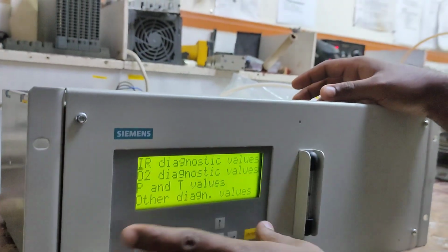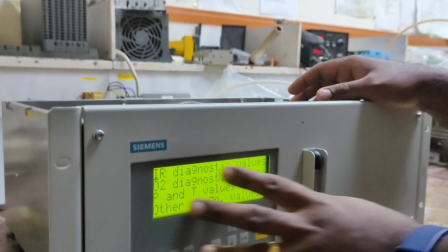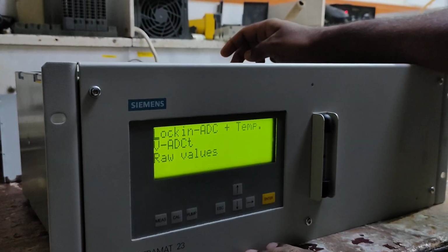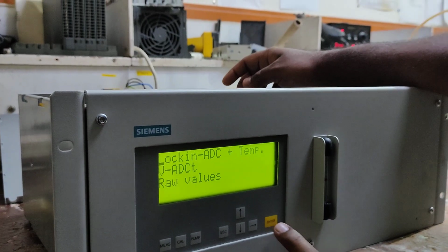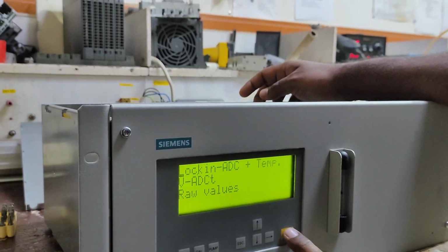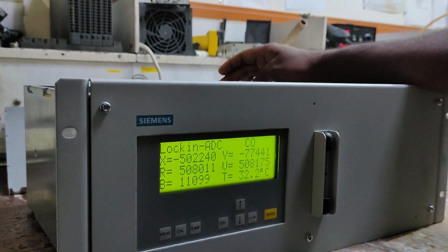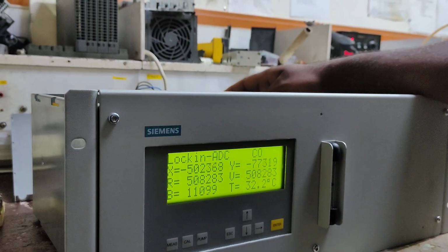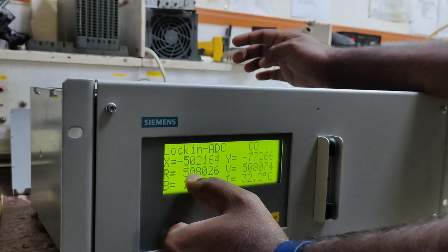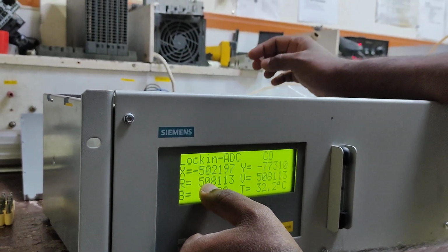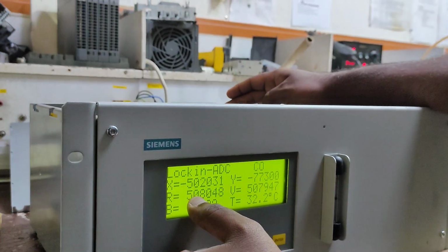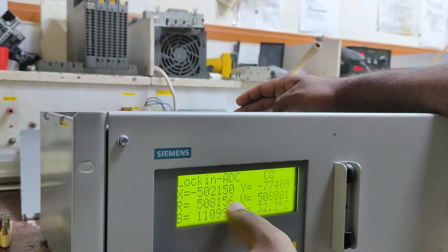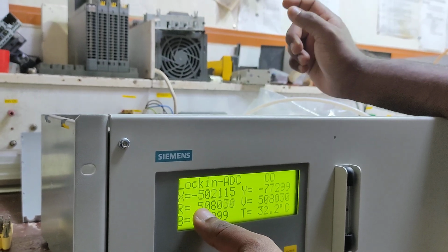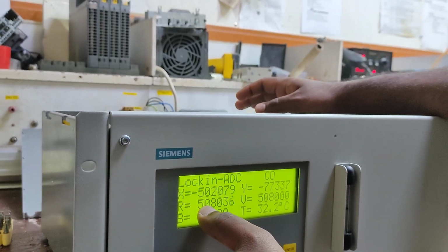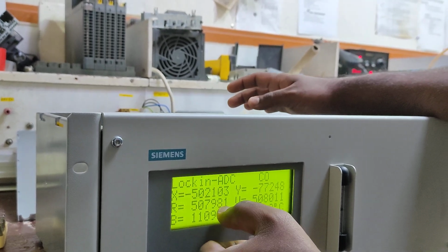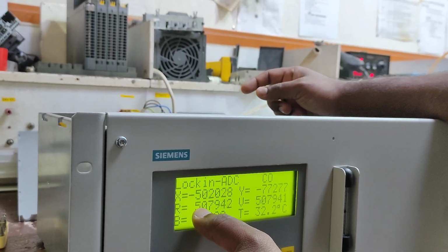Now this is a very important diagnostic value, the IR diagnostic value. When we say IR diagnostic value, we are talking about CO. Inside the CO IR diagnostic value, you have a lock-in analog to digital converter plus temperature. This is the place where it will tell you the resistance of the measurement. This R is the value of the Wheatstone bridge. You are now around 507,000. This is a digital value. It has nothing to do with analog ohms or megaohms. Because the analog to digital conversion is already done, these are counts. So this is around 500,000.